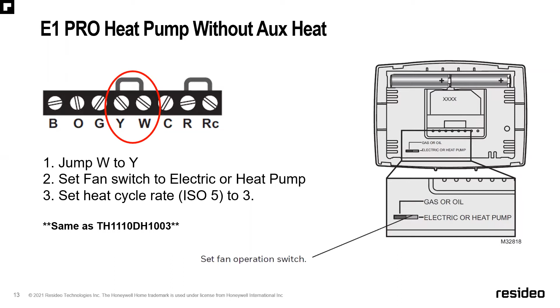Now if you are going to use the E1 Pro for a heat pump, what you'll need to do is jump the W and Y terminals. Then set the fan switch to electric or heat pump on the back, and set the heat cycle rate, which is ISO 5, to 3. That's the same as the Pro 1000 series you're already familiar with.